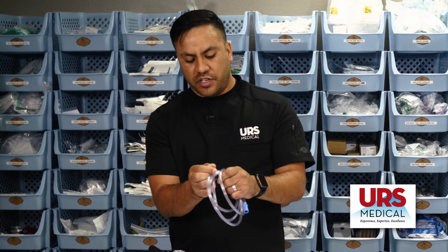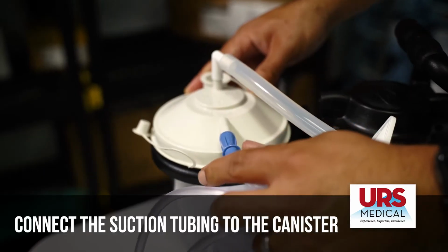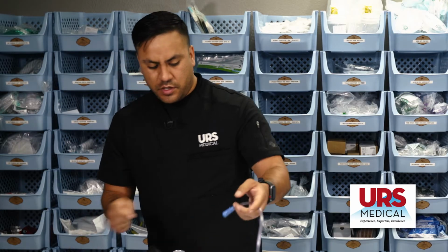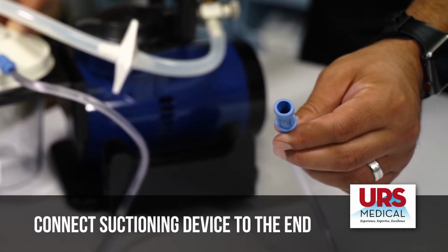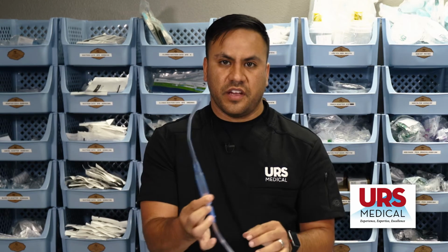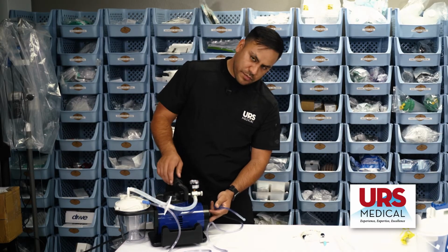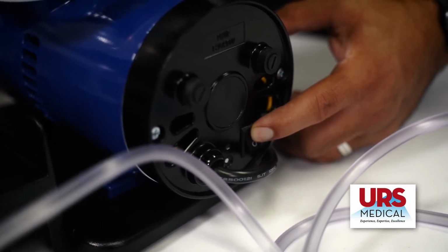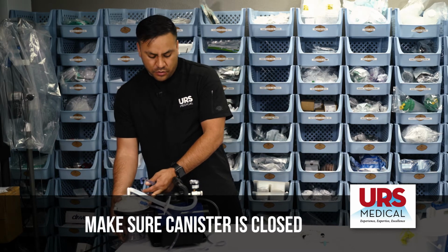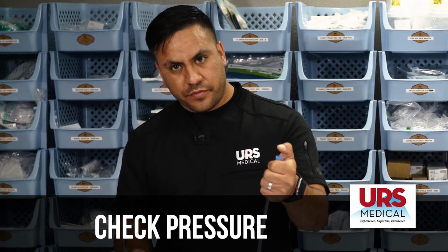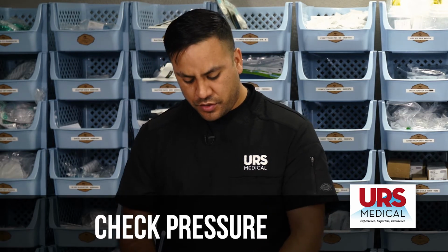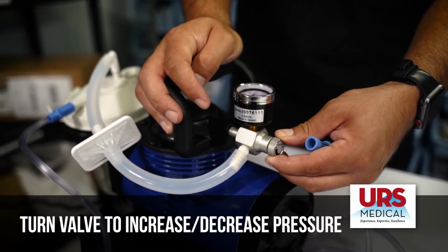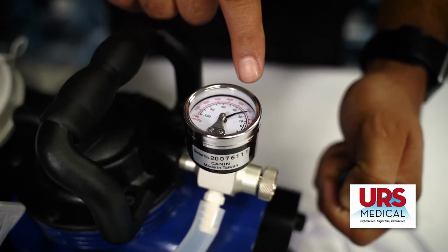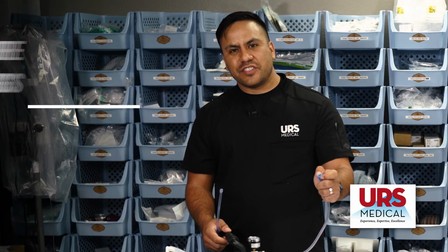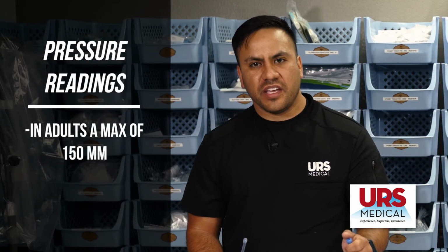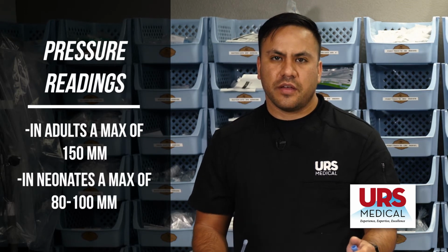Once that's assembled, you'll take your suction tubing, you connect it to the actual canister, and whatever suctioning device you'll be using, you would connect that to the end. In this case, it's a Yankauer. So when you turn it on, the power button's on the side. Make sure that the canister is closed and you check your pressure. If you need to increase the pressure, you turn to the right, and it would show an increase in pressure. In adults, you would want a max of 150 millimeters of mercury, and in neonates, you would want from 80 to 100 millimeters of mercury.